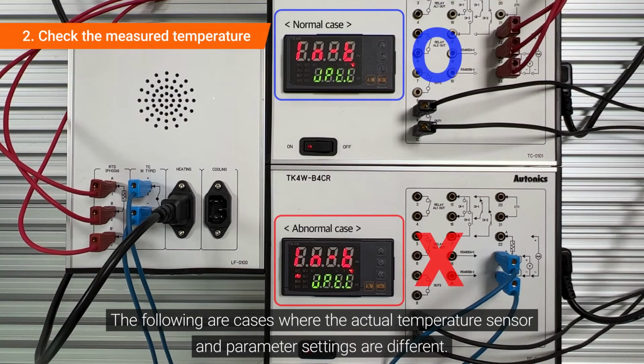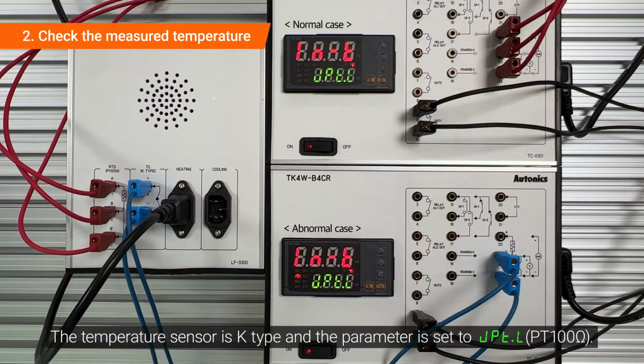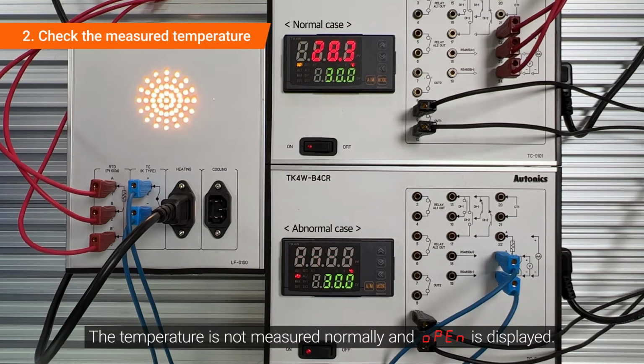The following are cases where the actual temperature sensor and parameter settings are different. The temperature sensor is K-type, and the parameter is set to JPT.L. The temperature is not measured normally, and open is displayed.